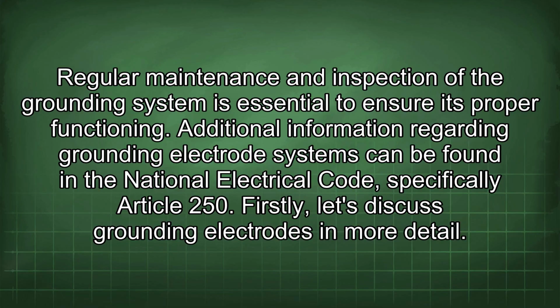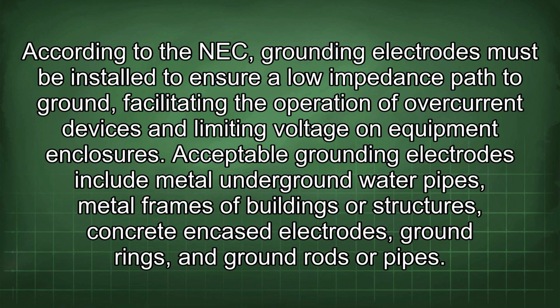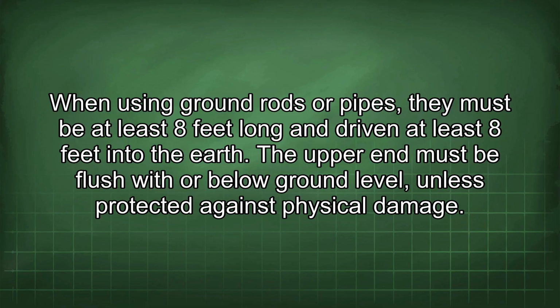Firstly, let's discuss grounding electrodes in more detail. According to the NEC, grounding electrodes must be installed to ensure a low impedance path to ground, facilitating the operation of overcurrent devices and limiting voltage on equipment enclosures. Acceptable grounding electrodes include metal underground water pipes, metal frames of buildings or structures, concrete encased electrodes, ground rings, and ground rods or pipes. When using ground rods or pipes, they must be at least 8 feet long and driven at least 8 feet into the earth.